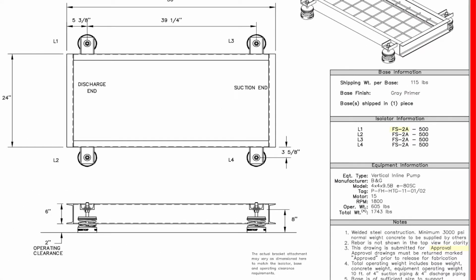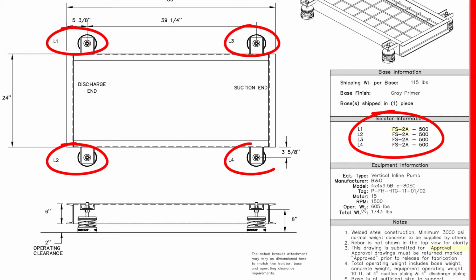For the heating water pumps, since there is equal weight on both the discharge and suction ends, take the total weight, 1,743 pounds, divide by 4 isolators, and round up to the next isolator capacity, which is 500 pounds. The 4 FS2A 500 isolators are listed here, and labeled L1 to L4 in the sketch. We'll talk more about the FS isolators next.